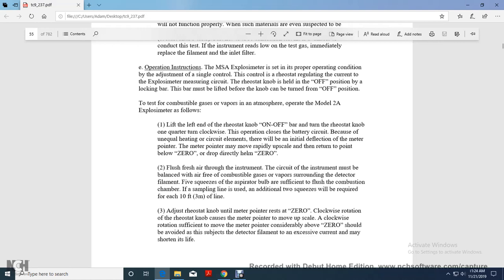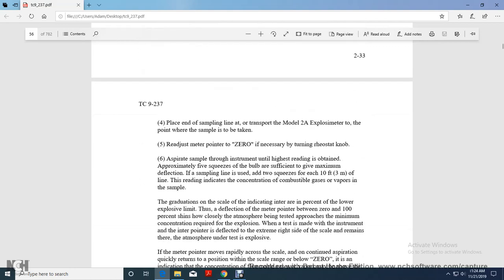Clockwise rotation of the rheostat knob causes the meter pointer to move upscale. A clockwise rotation sufficient to move the meter pointer just above zero is enough. Moving the pointer considerably above zero should be avoided, as subjecting the detector filament to excess current may shorten its life. Place the end of the sampling line. Transport the Model 2A explosimeter to the point where the sample is to be taken. Readjust the meter pointer to zero if necessary, using the rheostat knob.